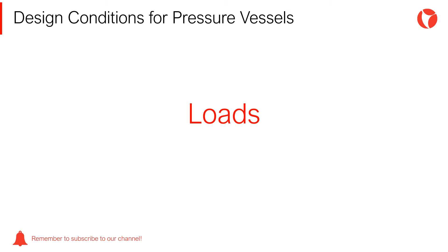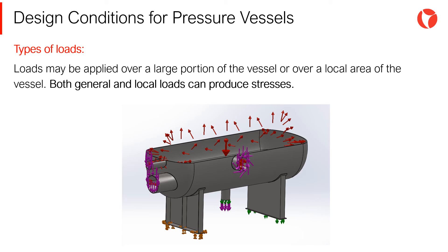Loadings or forces are the causes of stresses in pressure vessels. These forces and moments must be isolated, both to determine where they apply in the vessel and when they apply in the process. Loadings may be applied over a large portion of the vessel or over a local area. Both general and local loads can produce stresses, and these stresses are additive and define the overall state of stress in the vessel or component. Stresses from local loads must be added to stresses from general loadings, and these combined stresses are then compared to the allowable stress.